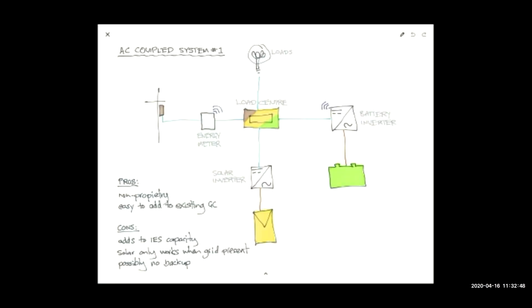So we've got another couple of questions. What happens when the grid drops out? Very good question, Paul. It depends is the answer. It depends very much on what type of system you have. So let's bring it back to, for instance, the first example, the AC coupled system. If the grid were to fail, so we sever our connection with the grid, as I've drawn it, the solar inverter will island immediately within 2 seconds. It's a requirement. And the battery inverter, as I've drawn it, will also island because it's required to comply with 4777.